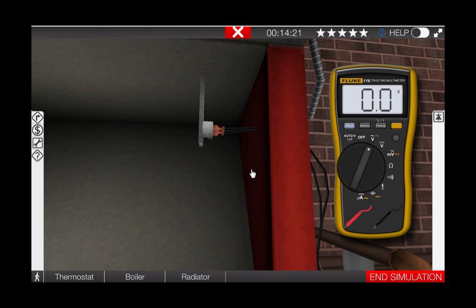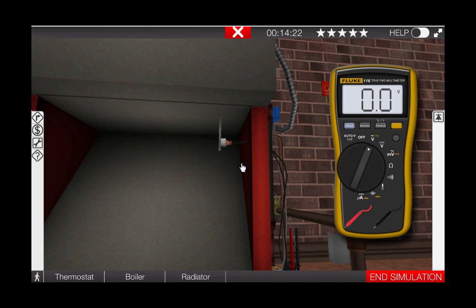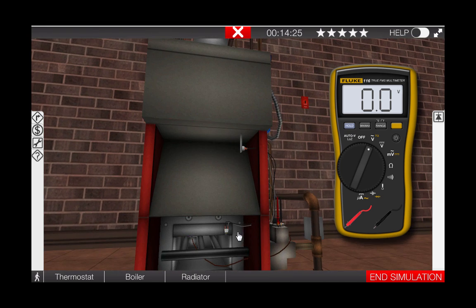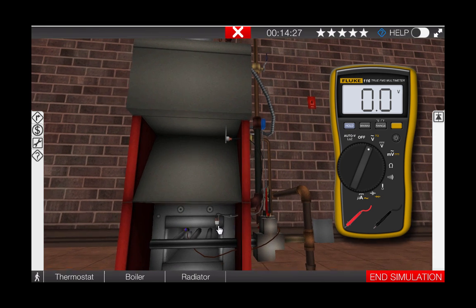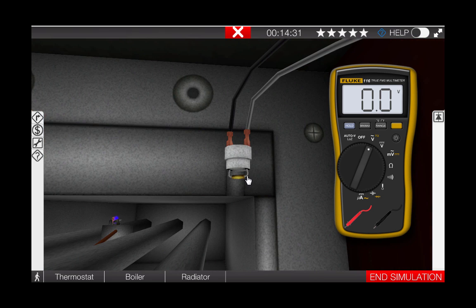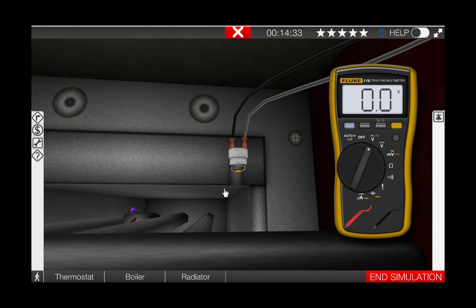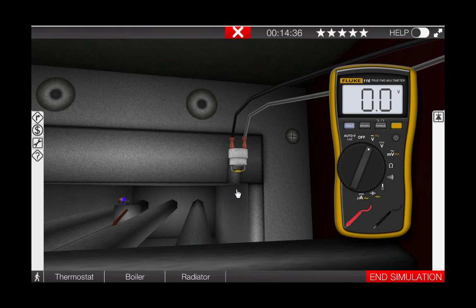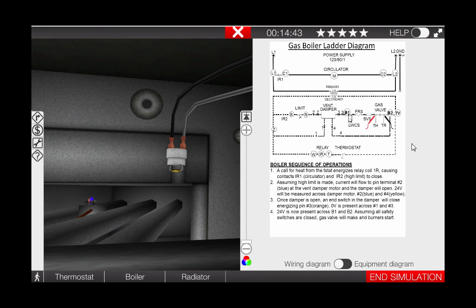Our third safety switch is the flame rollout switch, located right in the front of the burners. It looks very similar to the blocked vent safety switch, but the rollout switch protects against delayed ignitions due to poor air circulation or potentially dirty burners. If we review the wiring diagram for the gas boiler by clicking this tab on the right, we can see that all of these safety switches are placed in series to the gas valve.